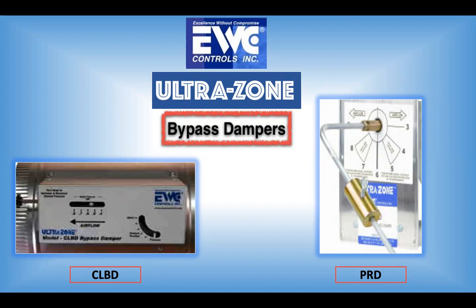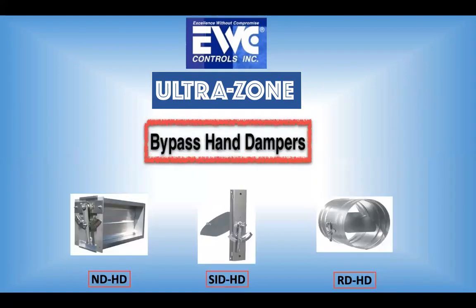The window on the right of that faceplate gives you our damper location. Now this will allow that blade to come open and also hold it shut when the design static is achieved. Now, the kicker: when we're doing any type of mechanical bypass, we need to install a hand damper, maybe more commonly known as a balancing damper. We need to incorporate that into the bypass duct.